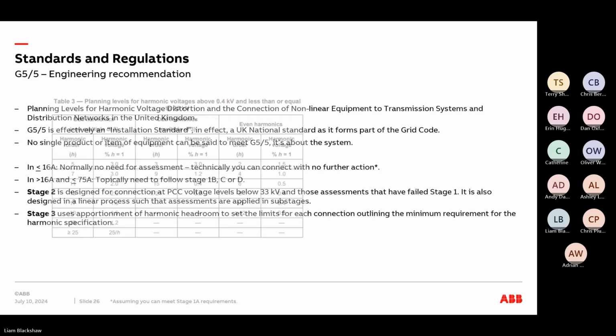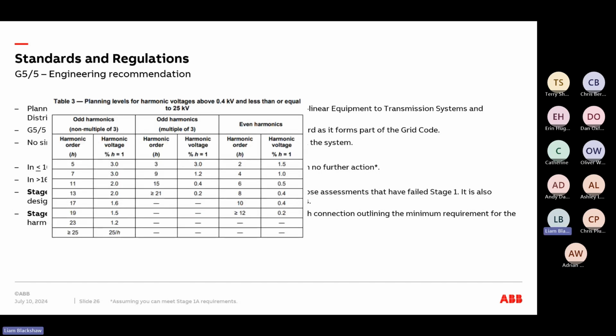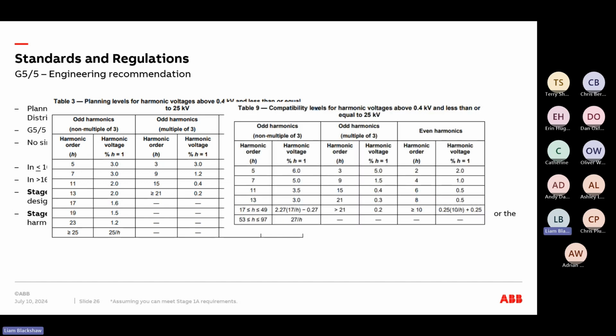And just to give you a bit of an idea, you have what we call tables in G55. I've taken this one, for example, which is the planning and compatibility levels for harmonic voltages above 400 volts but less than 25 kilovolts. They have planning levels and compatibility levels, and what you always tend to do is plan for the planning levels, try and aim for the planning levels, but you have a little bit of leeway in that you need to meet the compatibility levels.